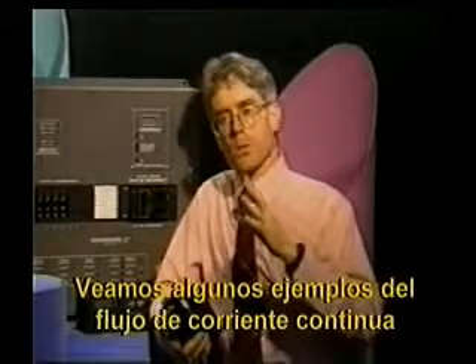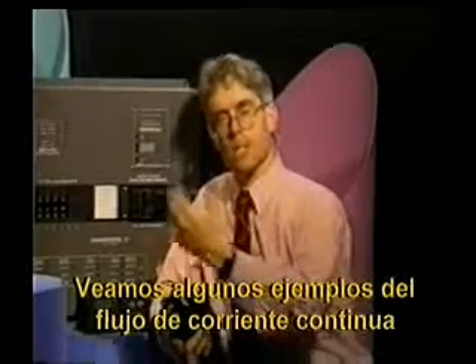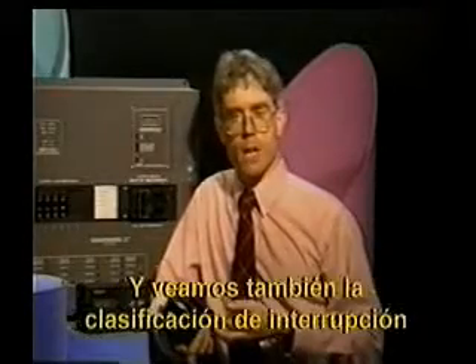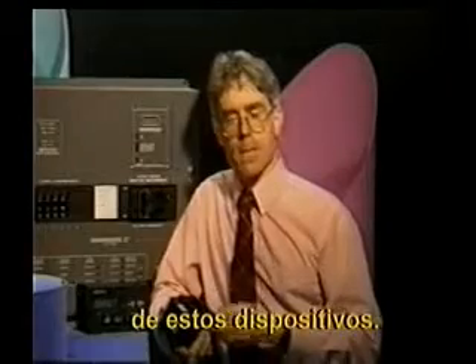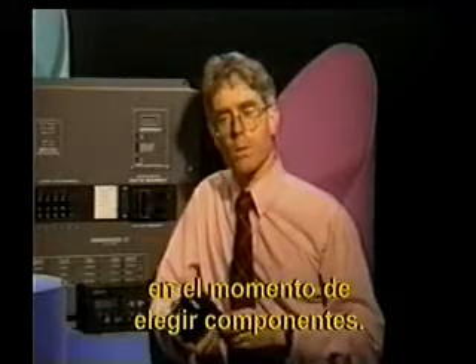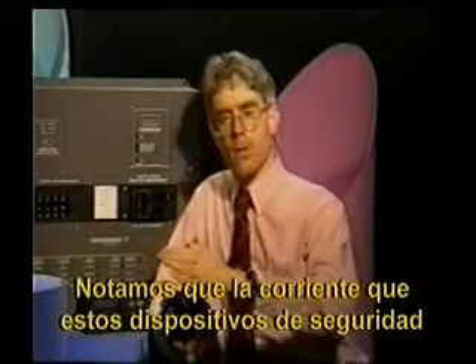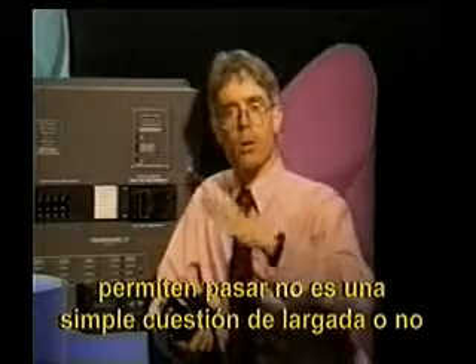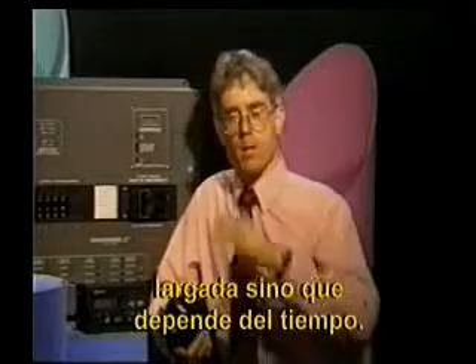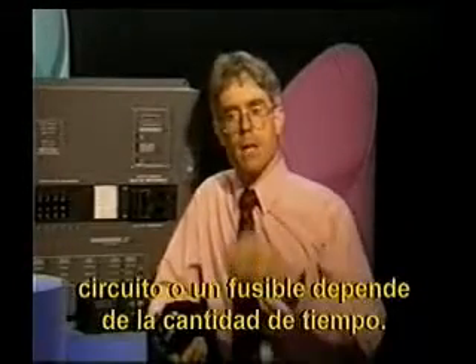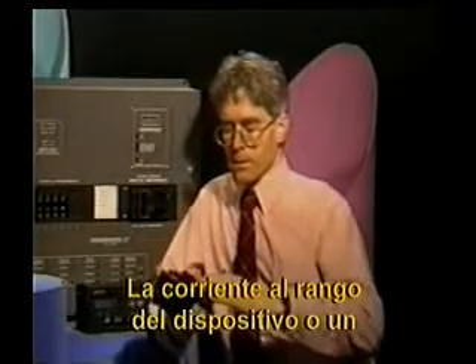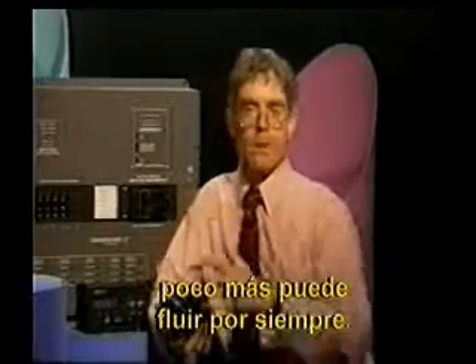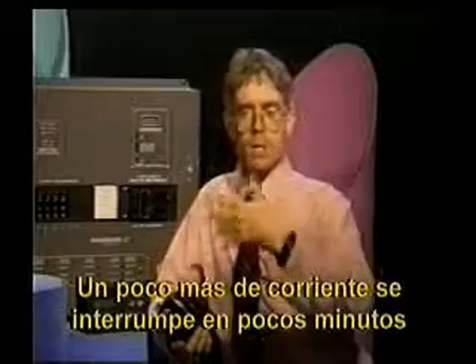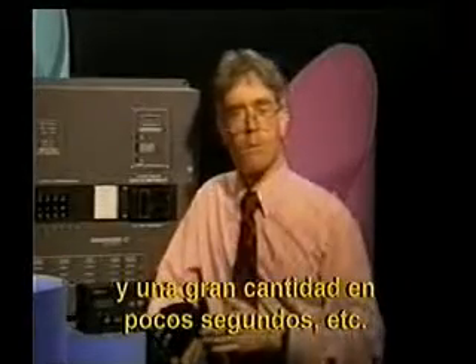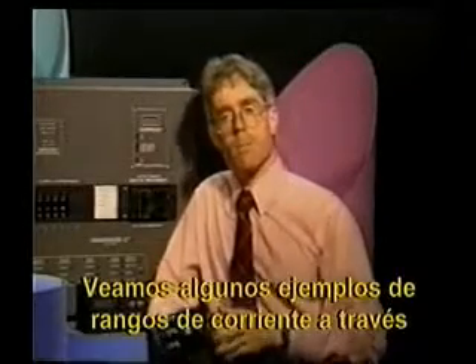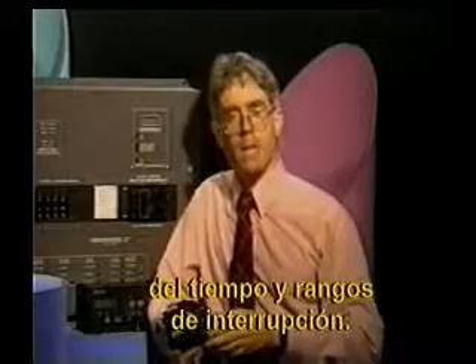I want to take a moment to look at some examples of both the continuous current flow that's allowed through fuses and circuit breakers, and to examine the interrupt rating of the devices. These are both factors that you should become familiar with when you're choosing your components. We'll notice that the current that's allowed through these safety devices is not simply a go, no-go kind of situation. It depends on time. The amount of current that's allowed to flow through a circuit breaker or a fuse depends on the amount of time. Current at the rating of the device, or slightly higher, is allowed to flow forever. A little bit more current is shut off within a few minutes. A vastly greater amount of current is shut off within a fraction of a second, and so on. Let's take a moment and look at some examples of current ratings over time and interrupt ratings.